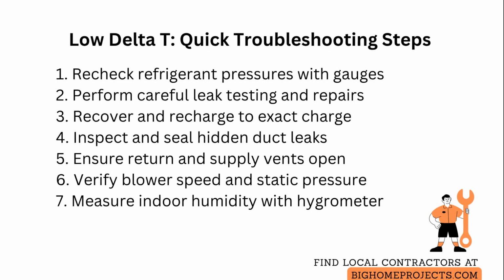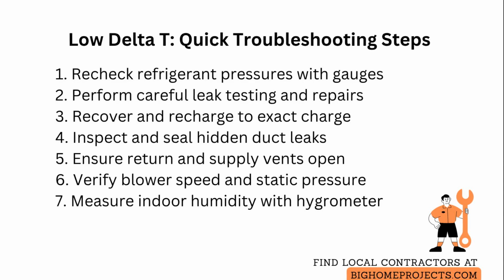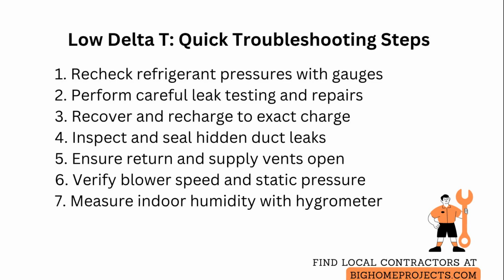Measure indoor humidity with a reliable hygrometer because high humidity can reduce apparent temperature drop even when the system is otherwise functional, and lower the thermostat set point during testing to get a clear reading.